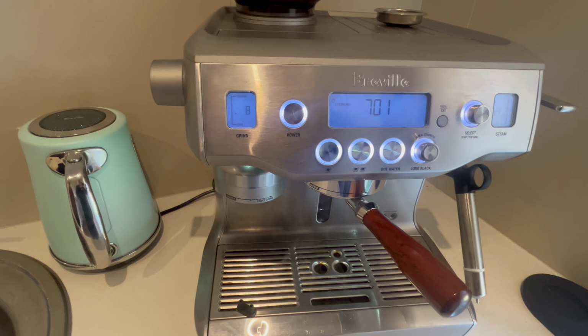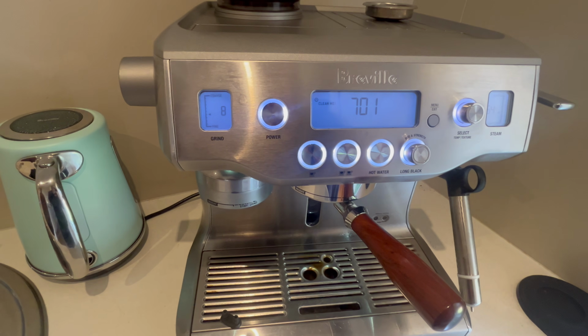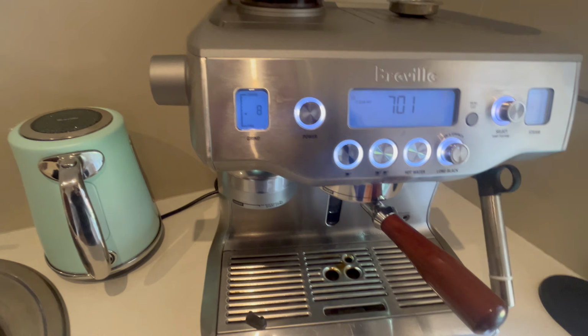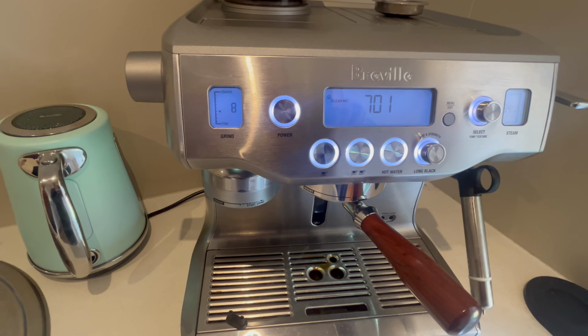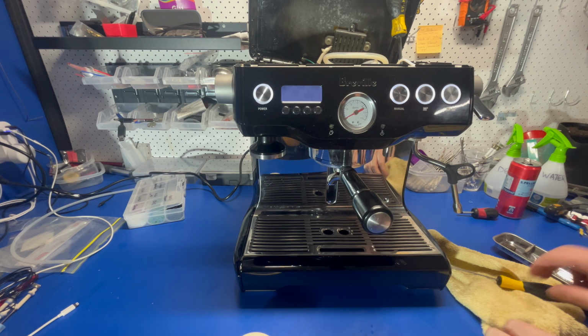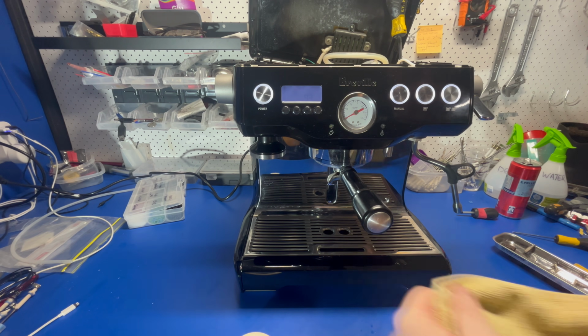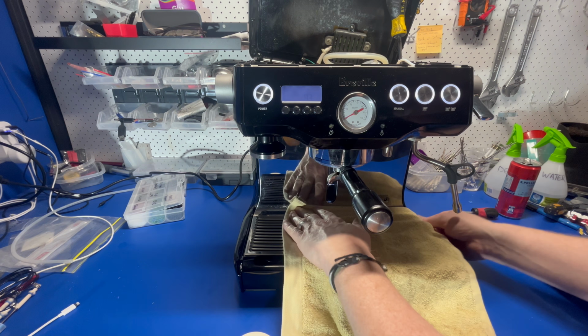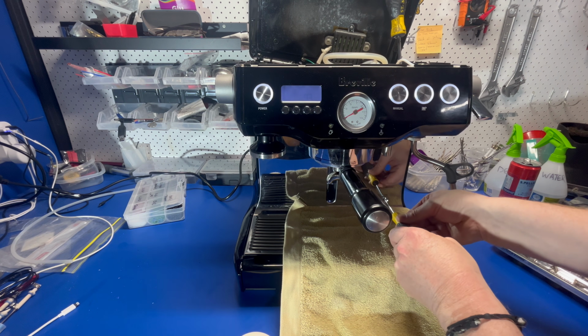You can see that the probes on this one are okay. It's well above the 391 set point. I think if you're much below this, say around 500, I'd be a little bit concerned about doing a descale. And then finally we have the dual boiler.